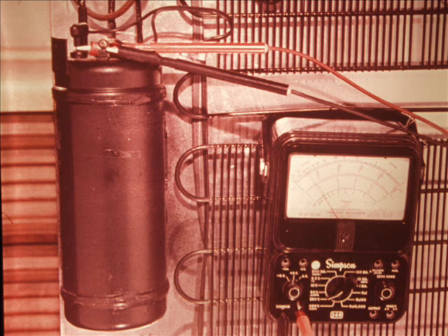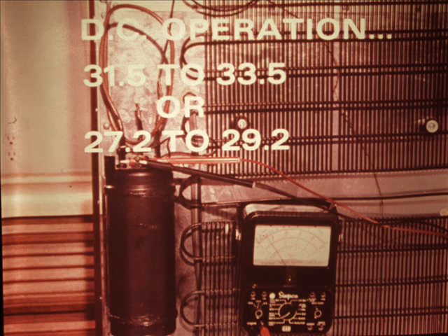With the 120 volt AC unplugged and operating on DC, measure the voltage with an AC voltmeter. Remember that on DC operation on the 7.5 cubic foot refrigerator, the meter will read between 31.5 and 33.5 volts, even though the actual voltage is 23 volts. On the 6 cubic foot model, it will read 27.2 to 29.2 volts AC. This is because of peculiar output characteristics of the inverter.